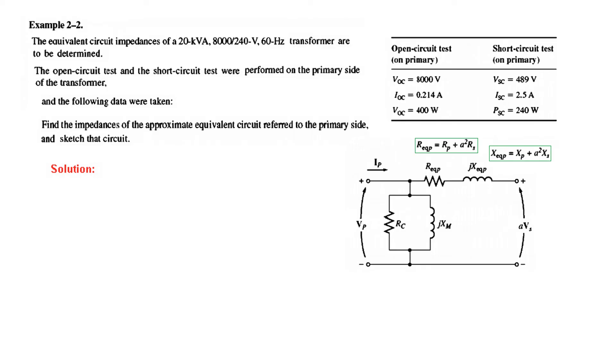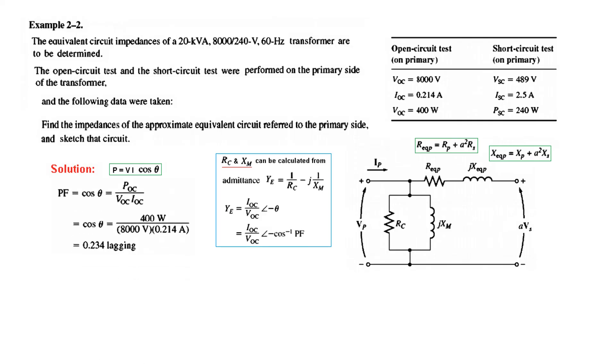So we have to calculate Rc, Xm and R equivalent and X equivalent. So we now have already derived all the formulas. So we'll just plug in those values. These were for the admittance components. And as we have, we know that P is VI cos theta. So from here, we can calculate cos theta which is power factor. So power factor is cos theta is equal to power divided by voltage into current. We know all these values from here. This is wrong. It should be POC. So 400 watt divided by the voltage divided by the current from the open circuit test.